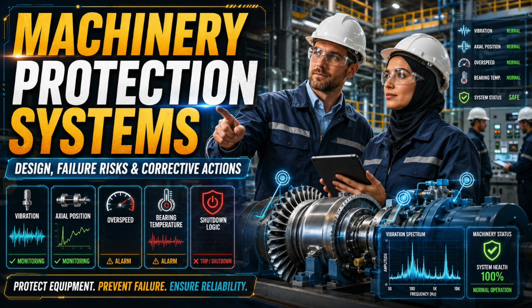Now, overspeed. Overspeed is the fastest and most unforgiving protection problem in rotating machinery. When overspeed happens, you do not have the luxury of long interpretation. The system must detect, decide, and actuate quickly, and overspeed protection must be independent, not shared, not casually integrated, not dependent on a process controller, not dependent on another system's sensor, not routed through unnecessary logic that can delay action. An overspeed detection system must be dedicated to the overspeed function. It must use independent speed sensing channels. It must apply proper voting.